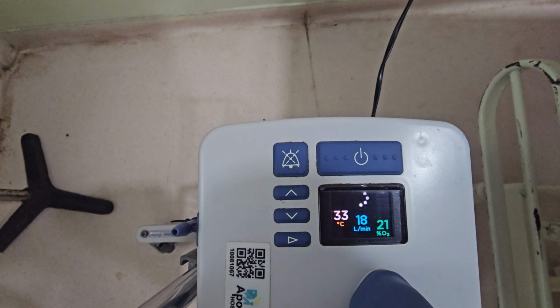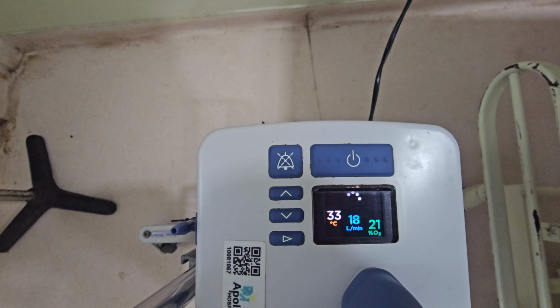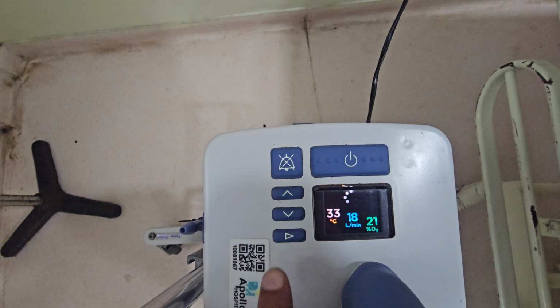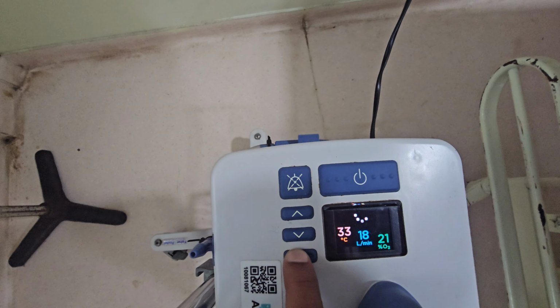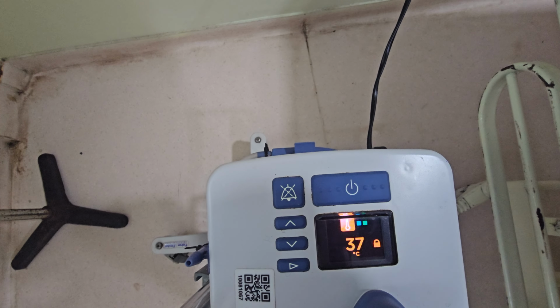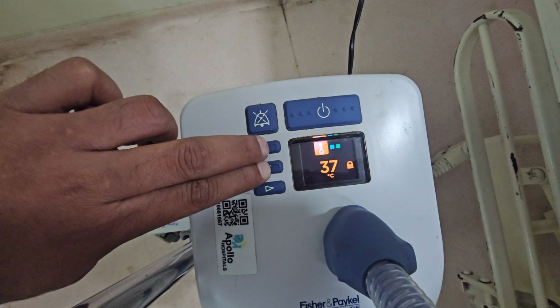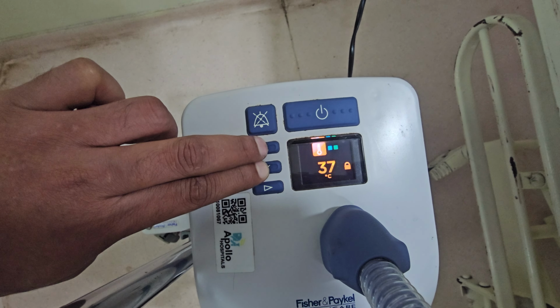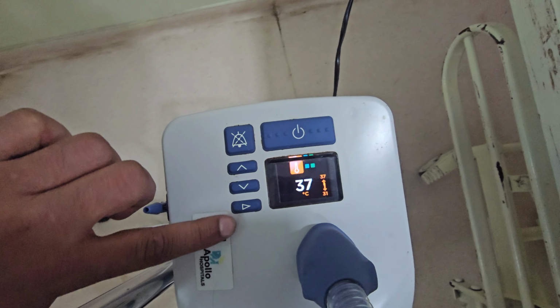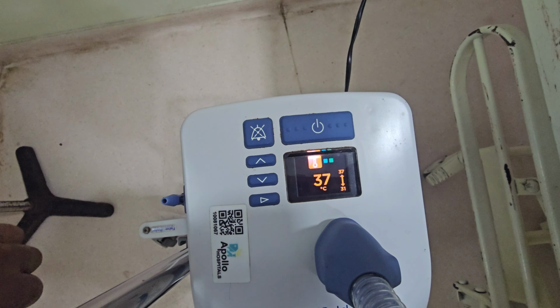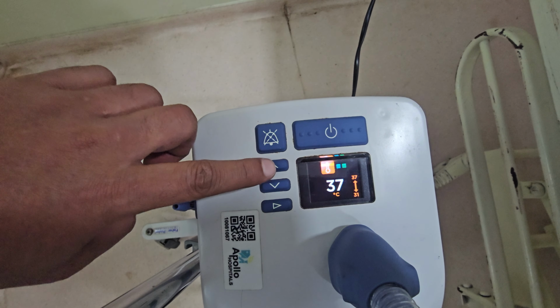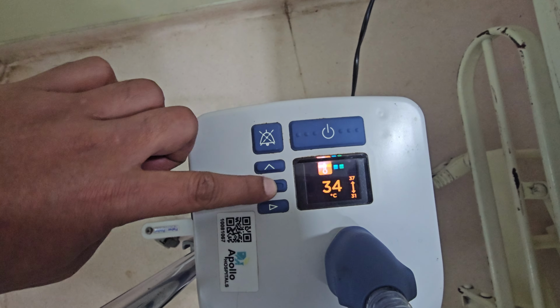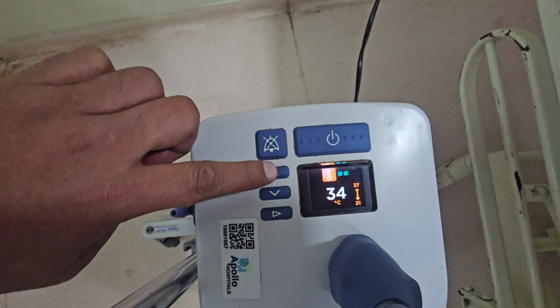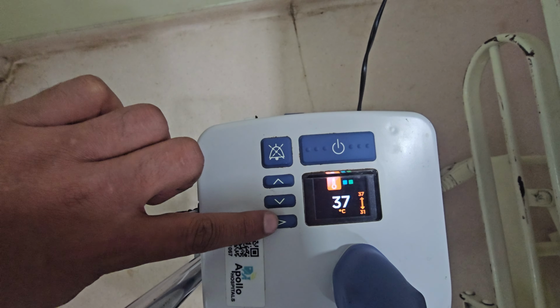On the screen, you can see temperature, flow and oxygen. To change temperature, press the play button. Now press the up and down arrows simultaneously. It will unlock the screen. Now you can scroll up and down to set the temperature. Press play, it will lock the settings. 37 degrees Celsius is the recommended temperature for adults.